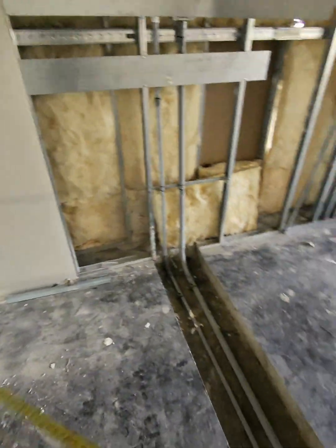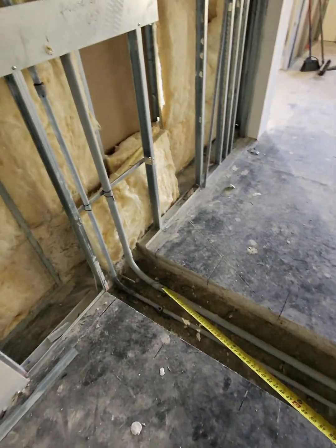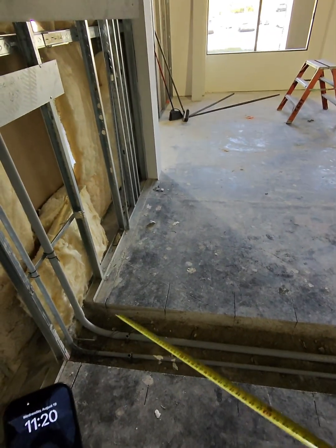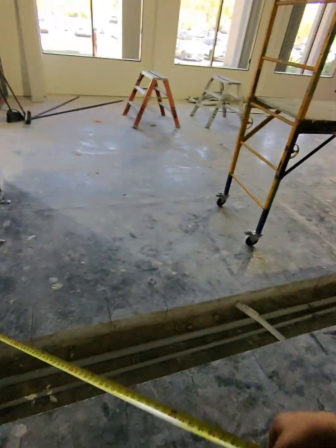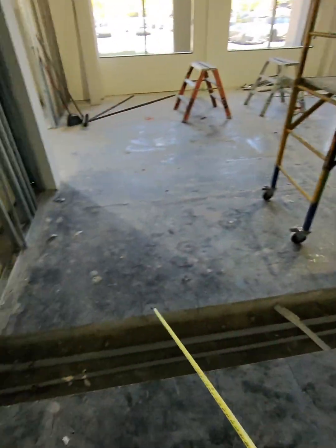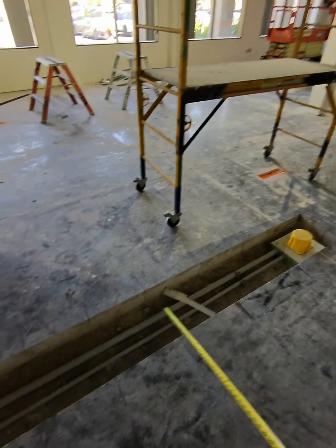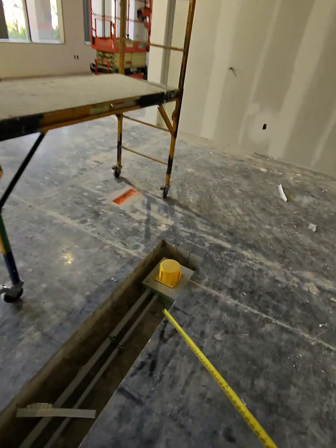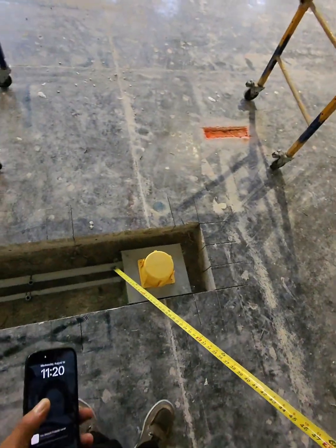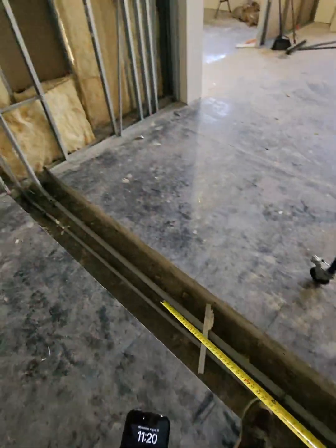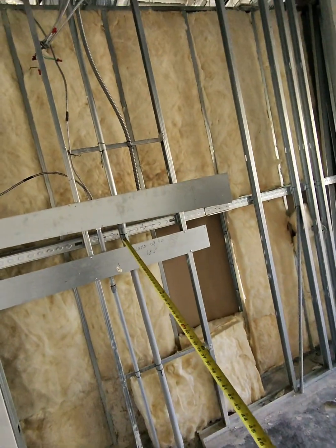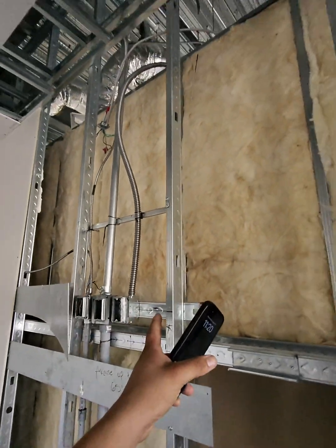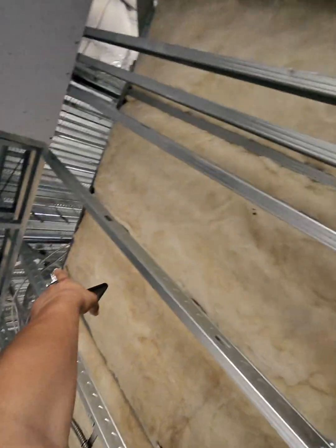We use 1/2 inch EMT to stake it down and tie wire it. Really, this is only necessary so that when they're pouring the concrete, this doesn't float up. It probably wouldn't float up anyway, but there's not like really supporting requirements. Although if this were code, it would be supported within code. But this is what we're looking for here. The connector, stakes, and a 90 up into the box. And then that's power, obviously. And then that's EMT going up. And just 90ing out, because that's for data.